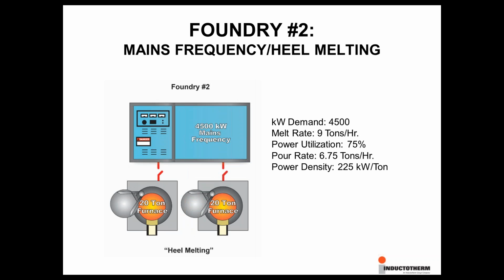In the Foundry number 2 example, also being a mains frequency heel melting system, operating at 4,500 kilowatts of demand. However, in this case, with the second furnace and with a butterflying operation, allows them to increase the power supply utilization to 75% and achieve a pour rate of 6.75 tons per hour. Although they're operating at 500 kilowatts of demand less than the previous example, because they increased their power supply utilization to 75%, they're able to increase their production at a lower kilowatt of demand.